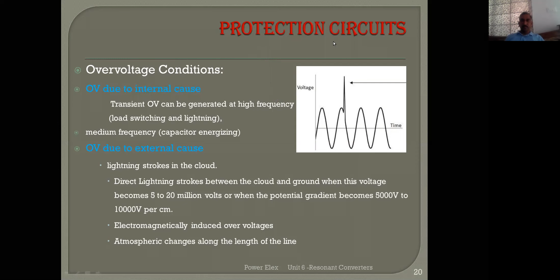Surges and sags are sudden overvoltages, but they don't last for a long time. They are always of short duration, so called a surge. And surge suppressors, MOVs, manage these attacks due to surge. Switching impulses, or switching of the load, typically heavily inductive loads, again generate an impulse which is a temporary overvoltage. It may damage the complete circuit. It may generate a spark between phase and ground and cause a breakdown in the insulation. Typically, if insulation is tested at 1 kV or 10 kV and the surge or temporary overvoltage is beyond that, it may damage your insulation.